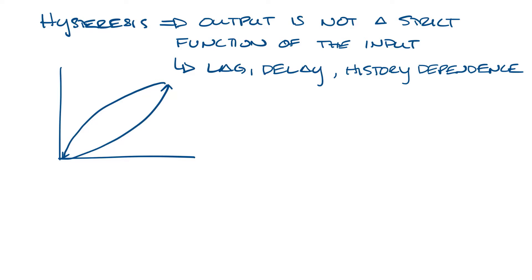So let's talk about this more specifically. Where do we see hysteresis in HVAC systems? Well, let's start with the old pneumatic systems. When a pneumatic thermostat signal increases, the controller CFM increases like this bottom curve, but when the thermostat signal decreases, it follows this top curve back down. So for example, if you have 11 PSI signal, it may be 500 CFM if the signal is increasing, but 1000 CFM if that same signal is decreasing.